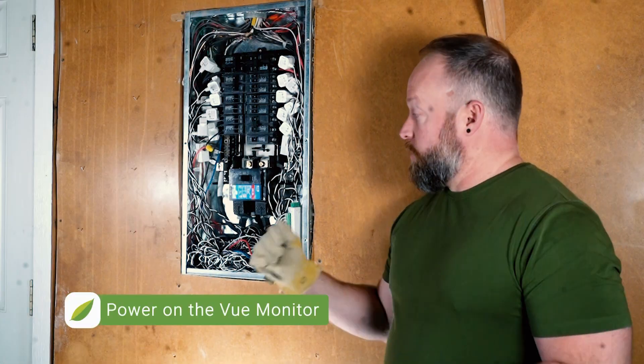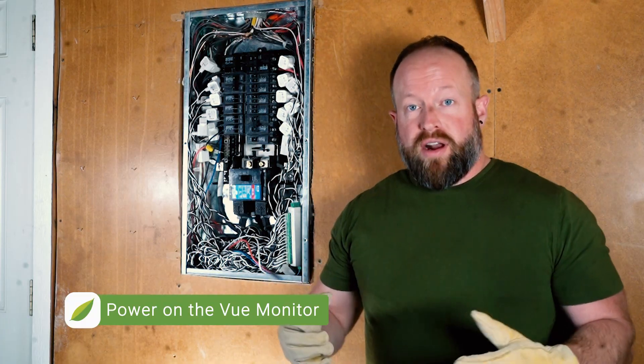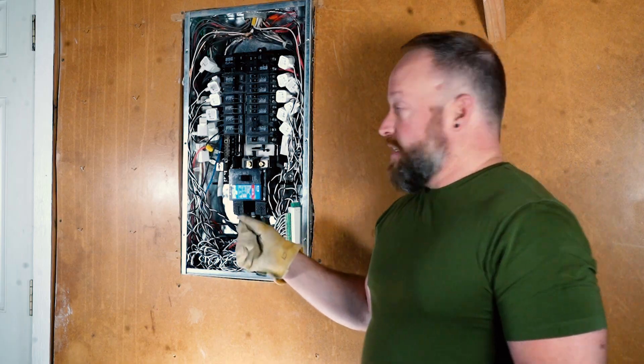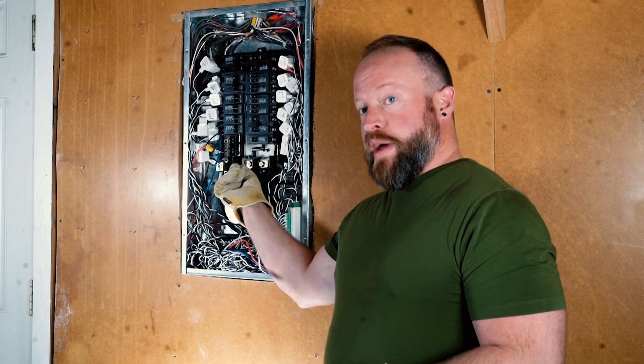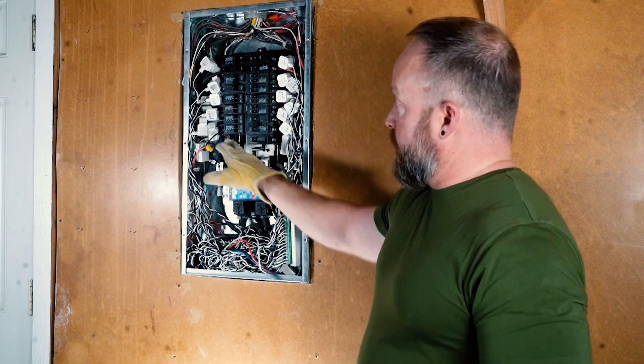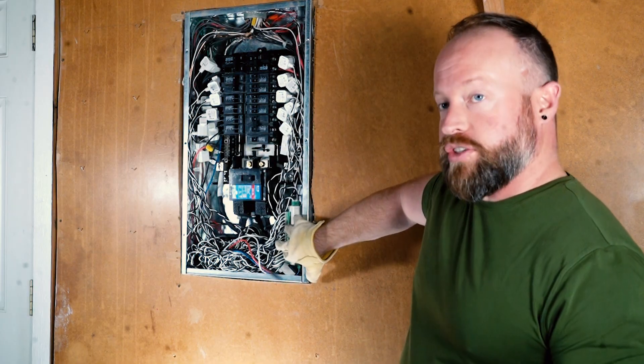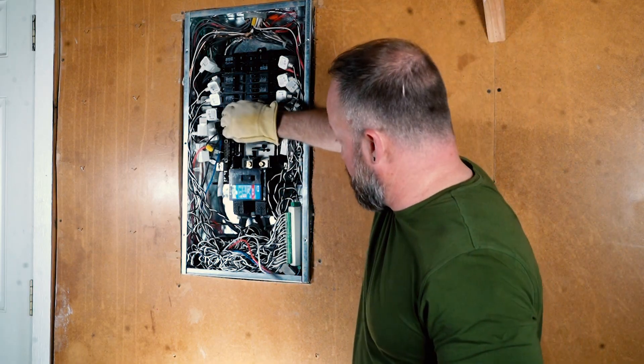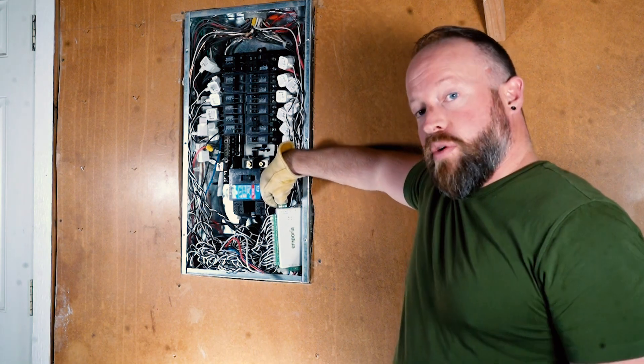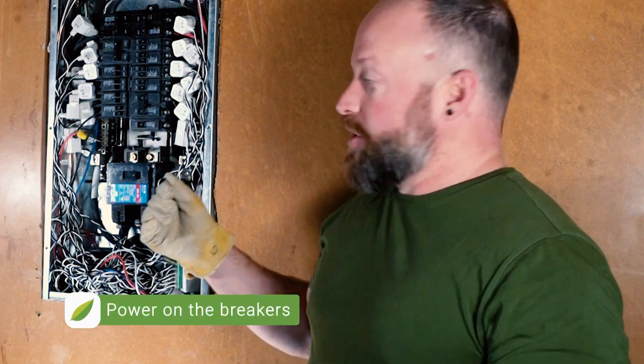Now that everything's in place and the unit is connected, it's time to power it on and make sure we connected it correctly. The way I'm going to do that is first turn on the mains power, and then I'm going to turn on the breaker to which the power connections for the Vue are connected. I should see the LED on the Vue turn on, and that's how we know we've connected it correctly. The Vue is powered up, it's time to turn on all the other breakers.